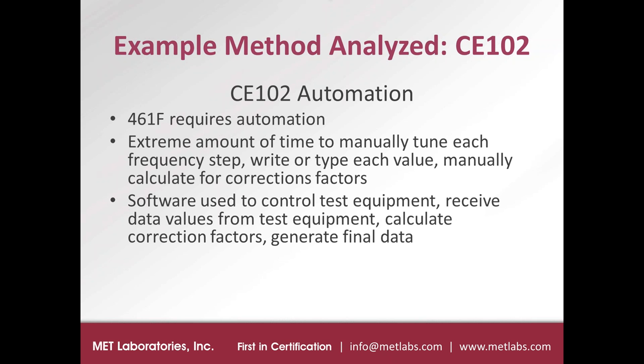And as I mentioned, CE102 is done with automation. It actually states in the standard that it requires automation. If you tried to do the test fully manually, it would take an extremely long amount of time to tune each frequency step and record the values and then calculate the correction factors. So software is used to control the test equipment, and it receives the data values from the test equipment, calculates the correction factors, and generates the final data.